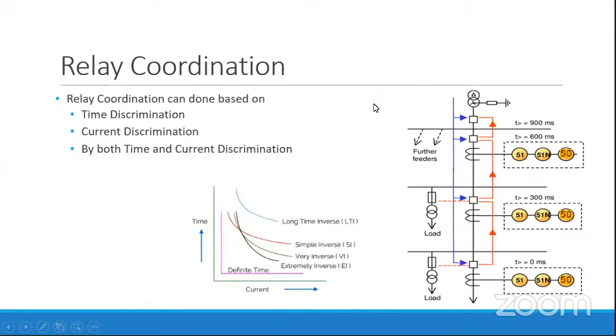For better understanding, let's look at the figure on the right hand side. Here you can see a typical single line diagram, with transformers feeding power to this network. This is the incomer feeder for this bus. Further downstream, it is feeding to another location, and then to the consumer end or another load center. For time discrimination, we should give time grading to the operation of the particular relays. Here you can see the CTs. This symbol is termed a CT, this is the symbol of circuit breakers, and this is the symbol of the protection relays used for the protection scheme.